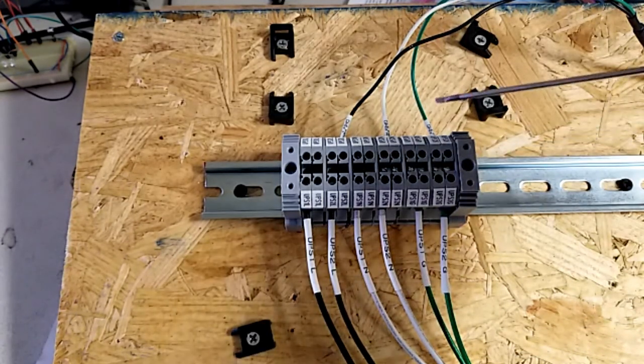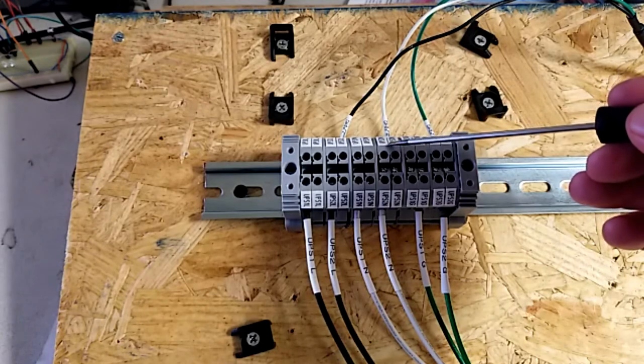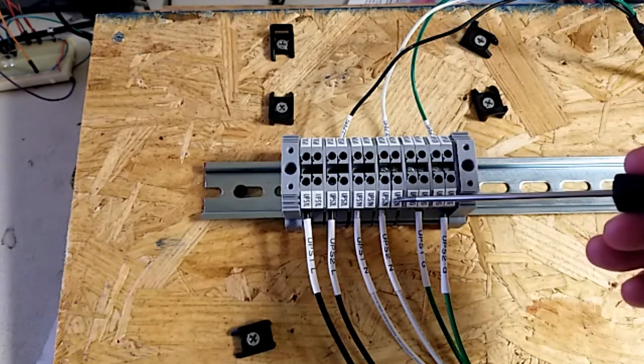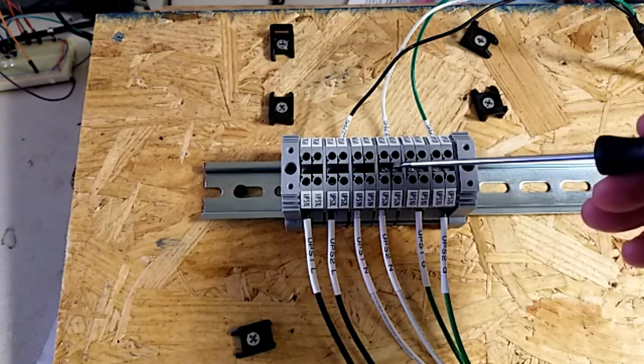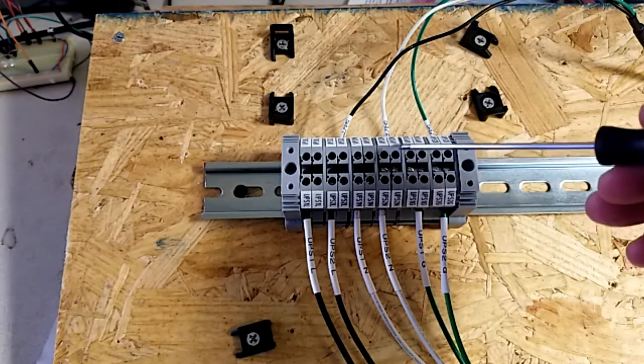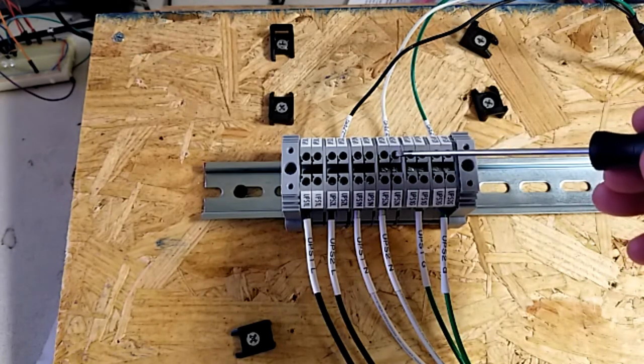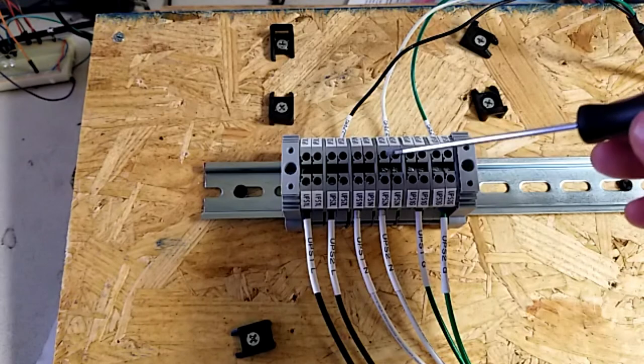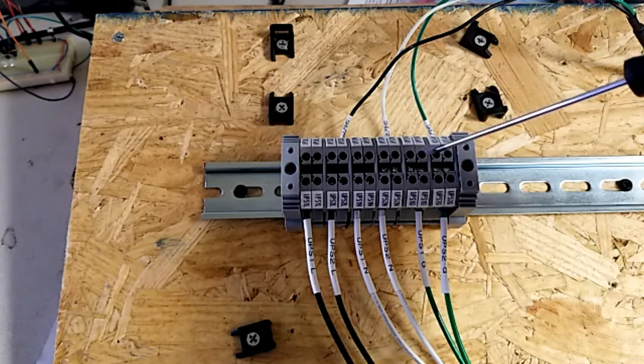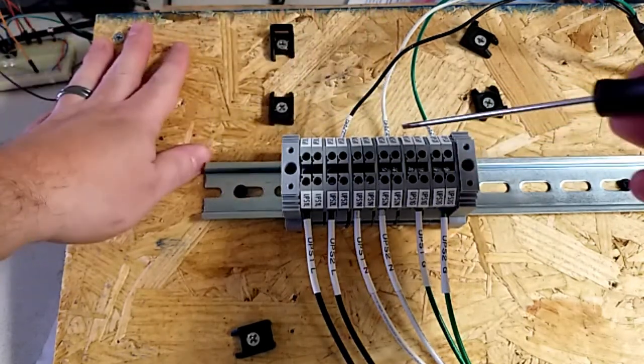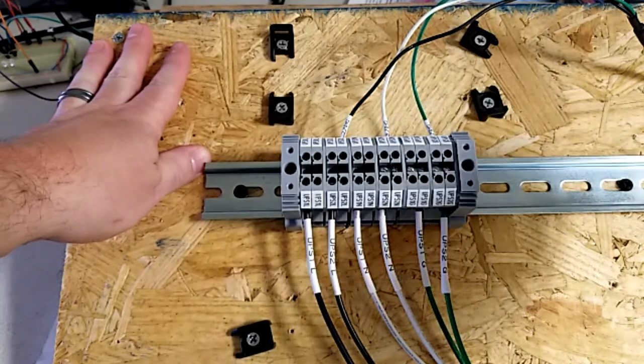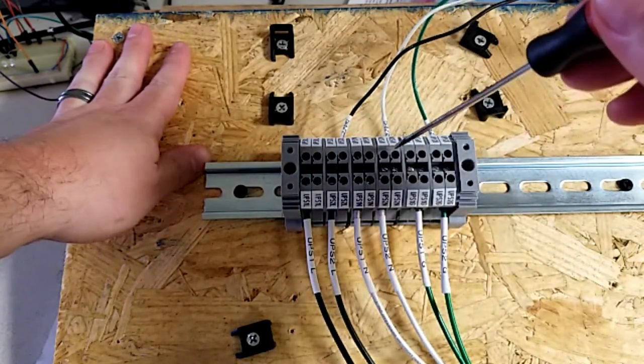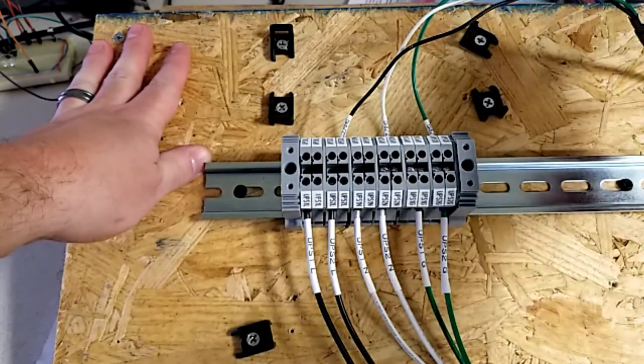So the first thing, the terminals that we're going to be replacing are these UPS2N terminals. This is jumpered together in a group, so we will be replacing the entire group, both sets of terminals here connected together. First thing that we're going to do, the PC power cord for PC4 is the one in question. It has a burnt neutral wire, likely from a loose connection here.